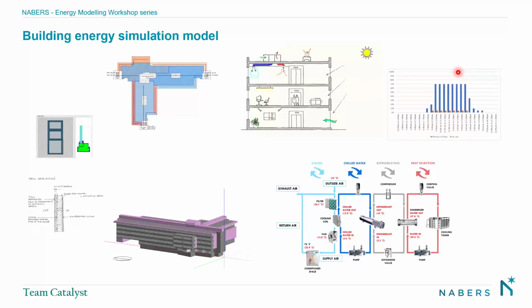Why that's important is that when the mechanical engineer designs his air conditioning system, he's designing it for full occupancy, 100%. He's sizing it for when all the lights are on, all the computers are working, everybody's at their seats, and it's a really bad, really warm day for cooling systems. That's a design day, as it's called.